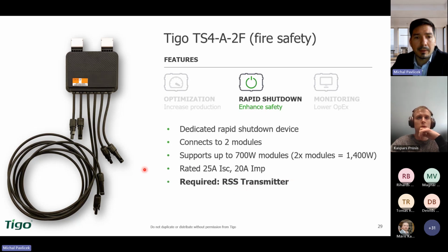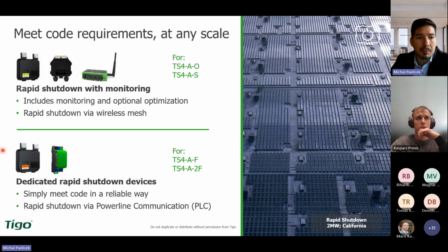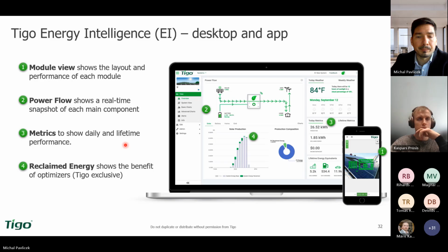For the correct functionality, you need the RSS transmitter. RSS transmitter looks like this. This is the unit which is sending a signal to the rapid shutdown control to control the safety. You see also large rooftops we do with this technology. So with O, the optimizer, you need the TAP and CCA as a complete. For the rapid shutdown TS4-A-2F, you need this one and the RSS transmitter.